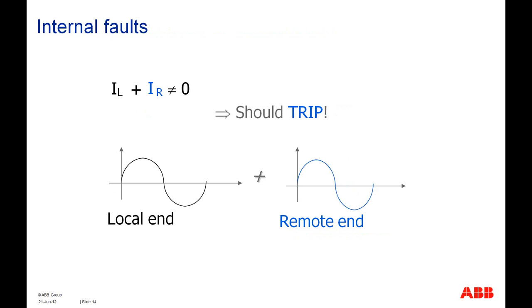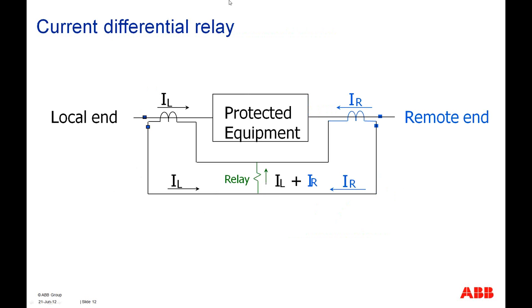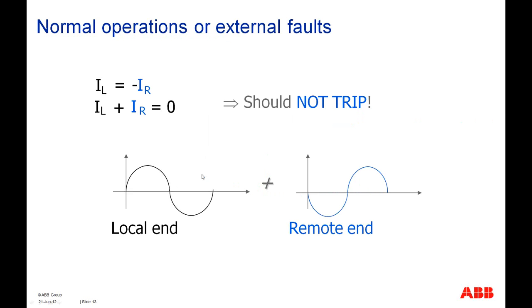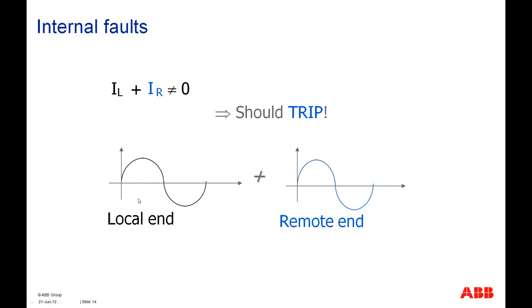But in the other case, if the fault is internal, like the figure shown over here, somewhere between these two CTs, then the algebraic or vectorial sum of both IL and IR will flow through the operating coil of the relay, and the relay will operate. So there will be a trip. You can see the local end current oscillograph and the remote end oscillograph are both the same, so they will add up, and the sum will not be equal to 0. They will add up to a certain value, and therefore tripping will occur. So that was the ideal situation, if the CTs are behaving ideally as per their characteristics.